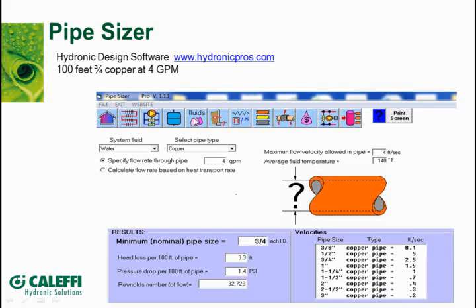But this one here, the fluids, is going to be important. I'll show you that. But I like the pipe sizer one here. And what you can do with this is, let's say you've got a system that you want to purge out that you put in. You go, well, what kind of flow rate do I need? How am I going to get that velocity up around that 2 to 4 feet per second?